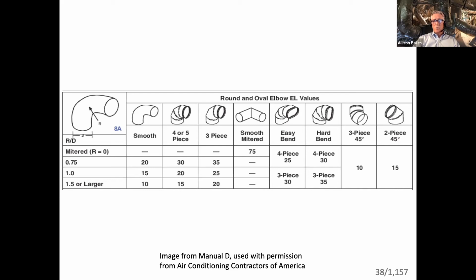I change my filters about every 6 months, and if the filters are sized the way I talked about here, they can go for a year or 2 years without the pressure drop being bad enough to affect the performance. When I changed mine the first time, I think it was 6 months, and I think the pressure drop hardly changed. It was a little bit worse, but not much worse. I have an article about that. I don't remember what the numbers were, but it did get a little bit worse.